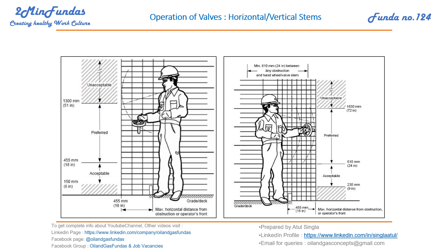There are various elevations which are acceptable and some which are not. If an operator is standing and trying to operate a valve with a vertical stem, from 455mm up to 1300mm is the preferred elevation of the stem. The operator can stand and operate this valve very easily within this range — this is the preferred one.